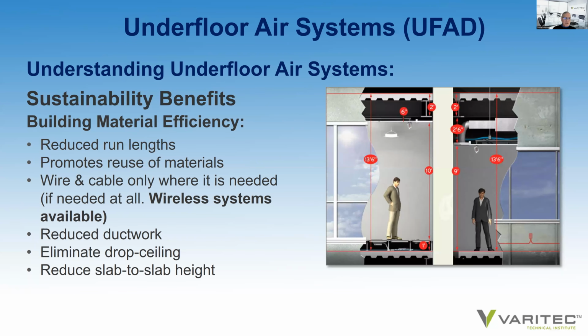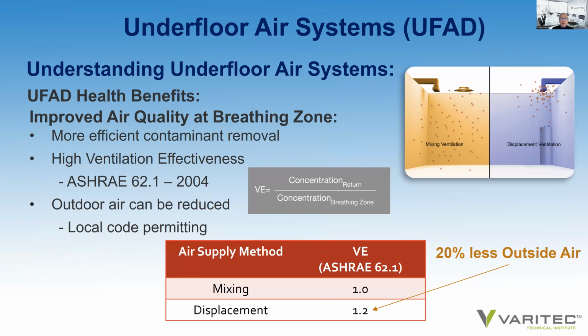There are a lot of architectural aspects that benefit from UFAD that should be included in any building owner's evaluation of which system to apply. ASHRAE recognizes the effectiveness of UFAD systems, and it has assigned it a ventilation effectiveness rating of 1.2, which means if applied, 20% less outside air is required to meet code. And 20% less outside air does offer a lot of energy efficiency.